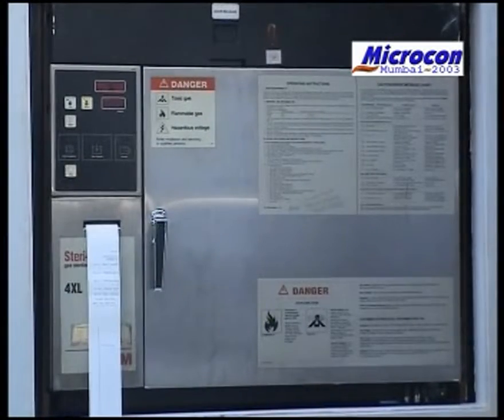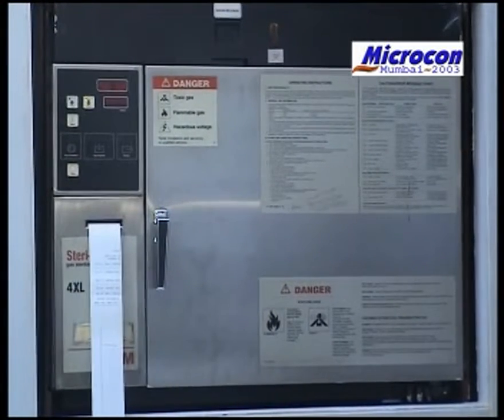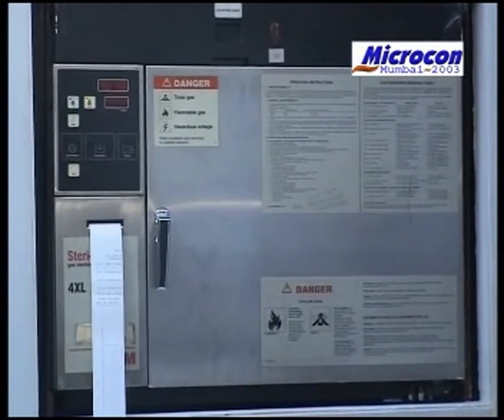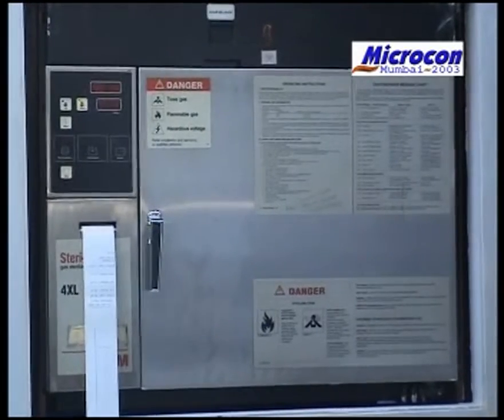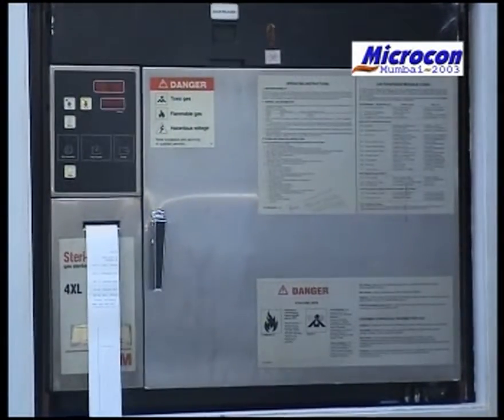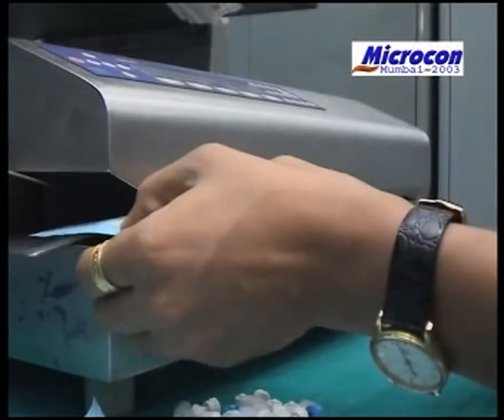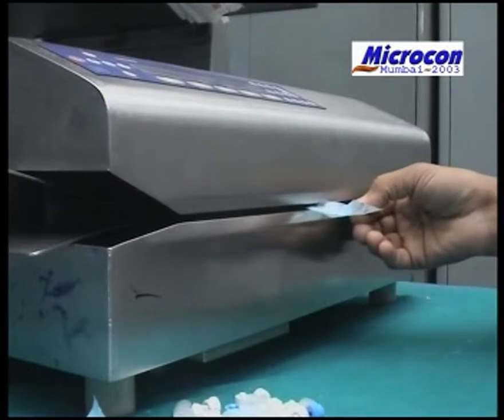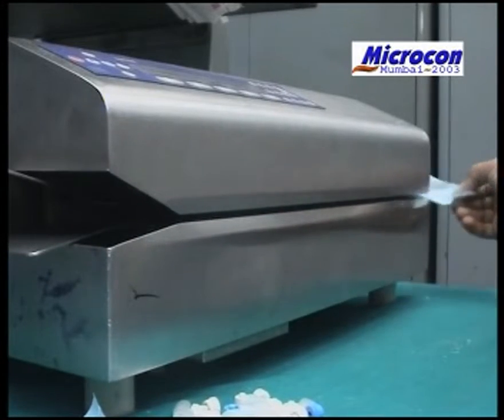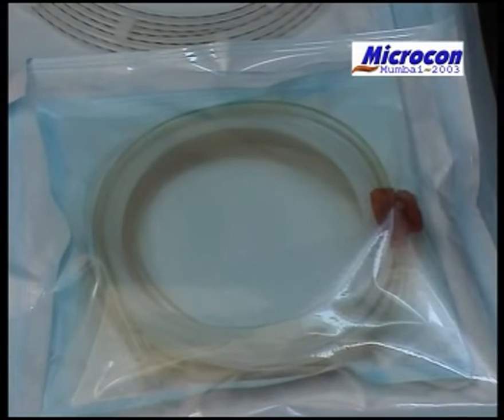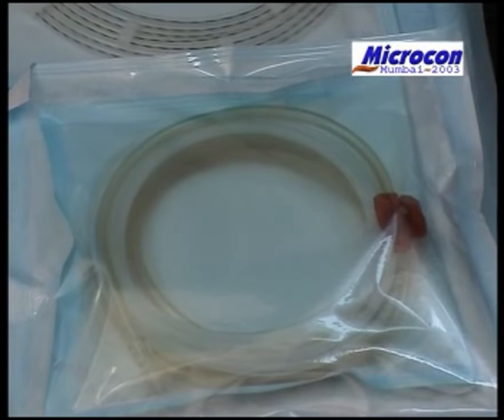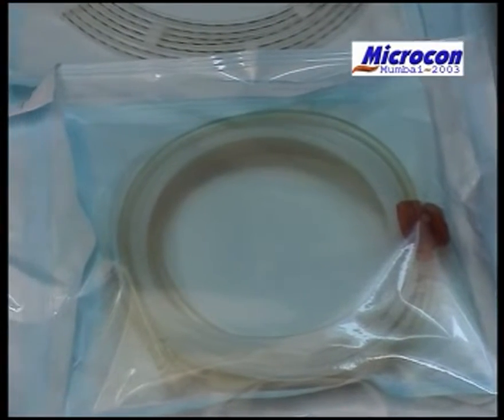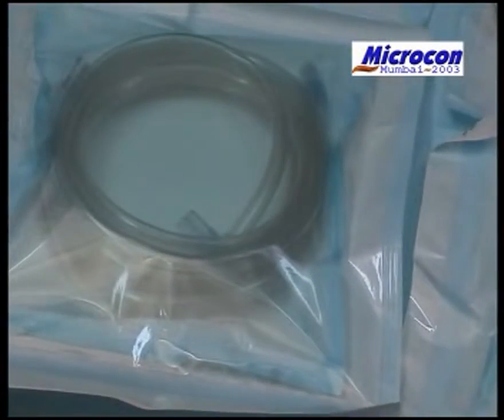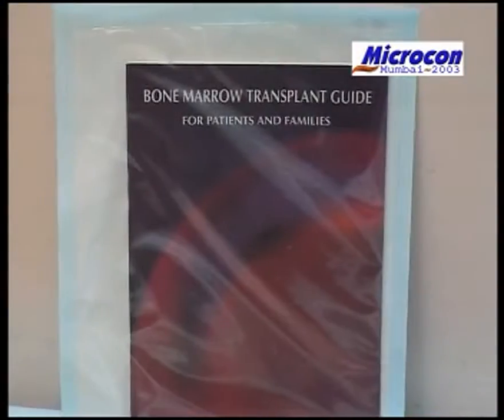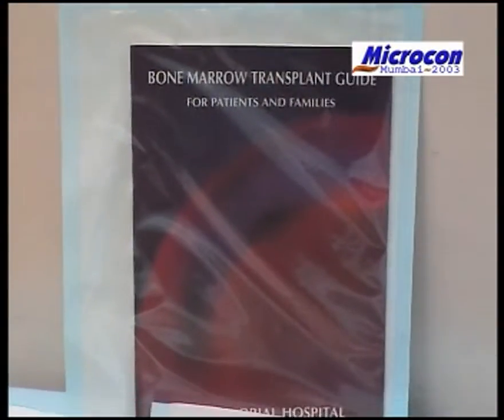Ethylene oxide is the second commonly used method of sterilization. However, the ETO gas is carcinogenic and requires special precautions. The packaging for ETO is different, with plastics, and one more crucial step that needs to be borne in mind is aeration of treated items, which is a must to prevent residues of the gas.